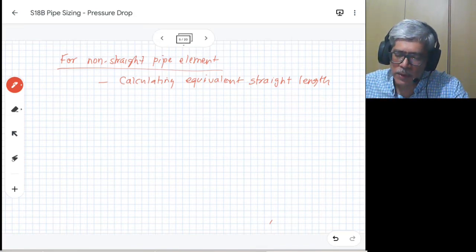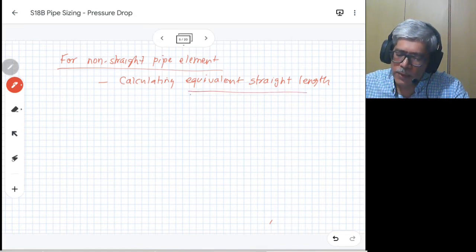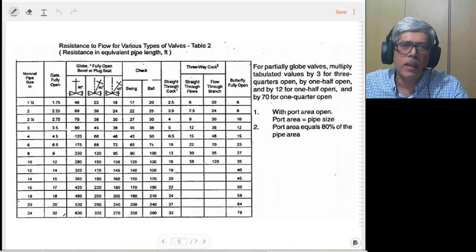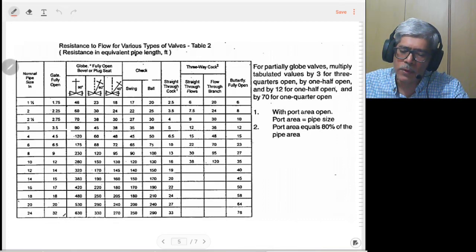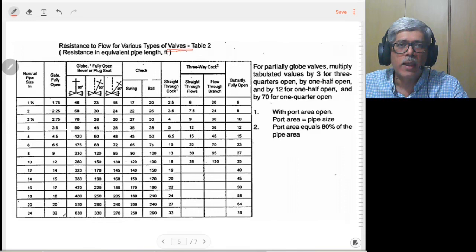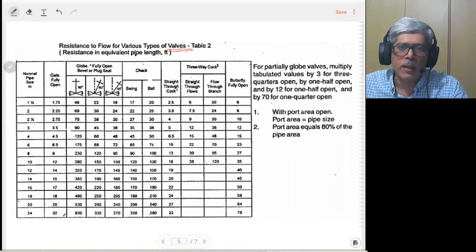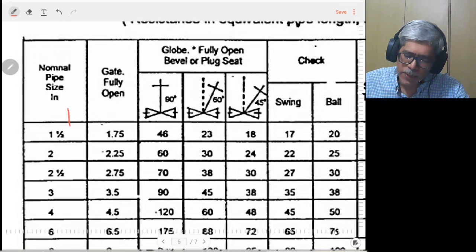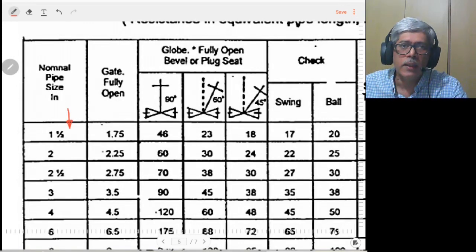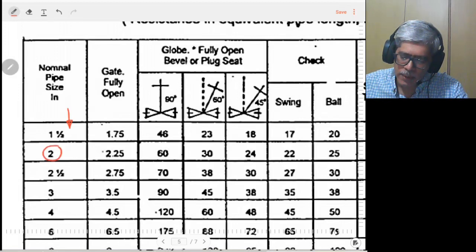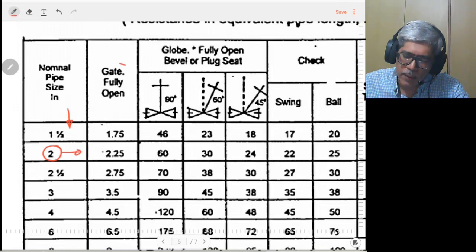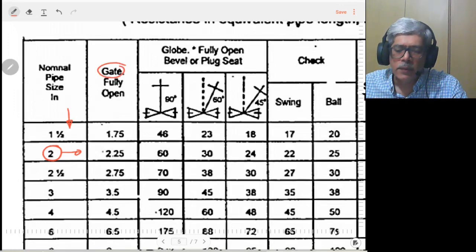For calculating the equivalent straight pipeline for different items, different tables are available. What we are looking at here is the table for valves — for different types of valves, how to calculate the equivalent straight length is given in this table. The first column has the pipe size in inches. For example, if you have a valve on a two-inch pipeline, you consider the two-inch row and determine the type of valve. Let's say your valve is a gate valve in fully open condition.